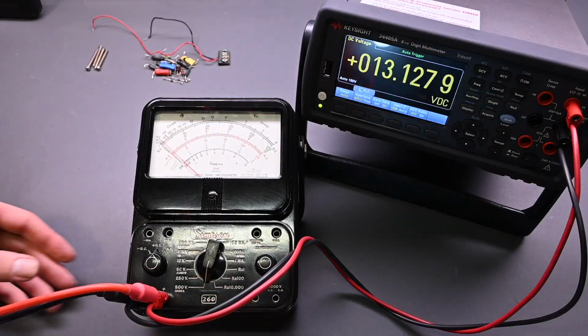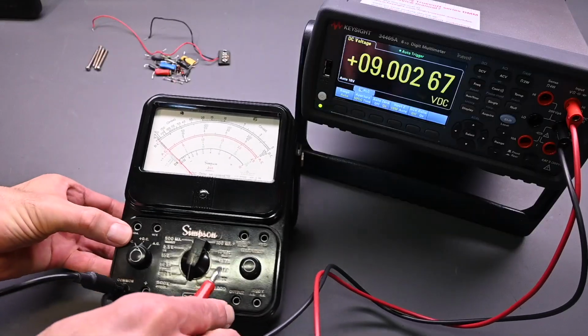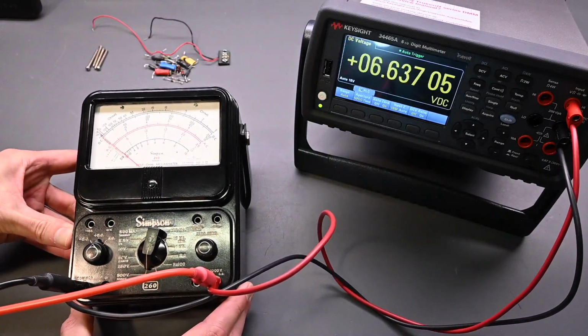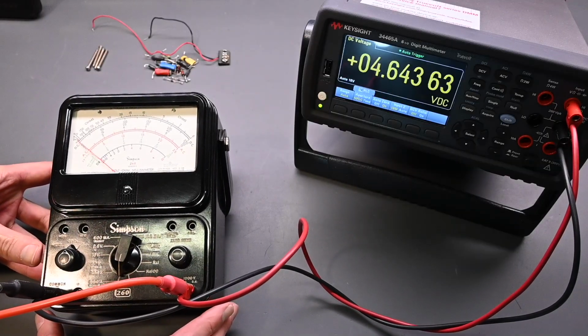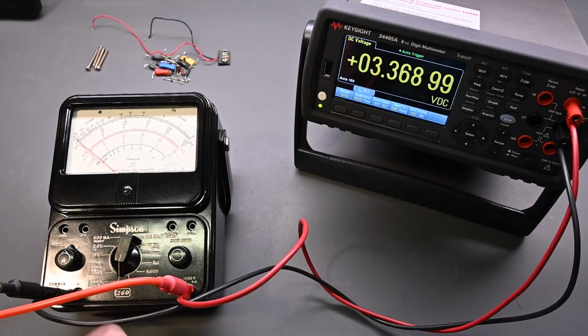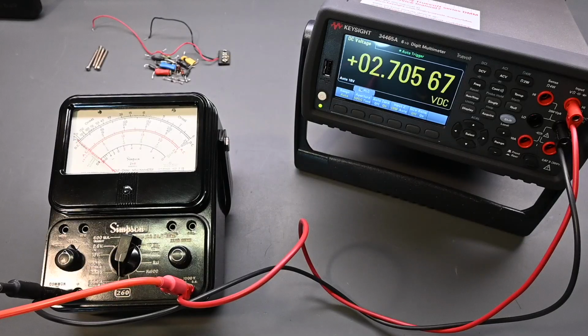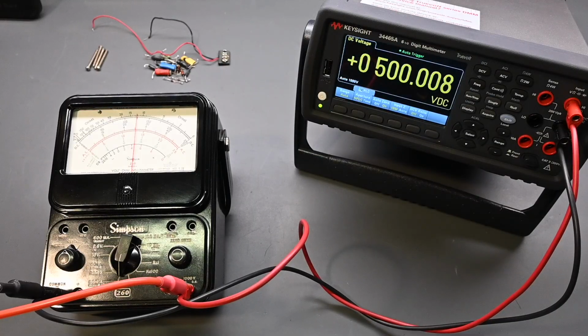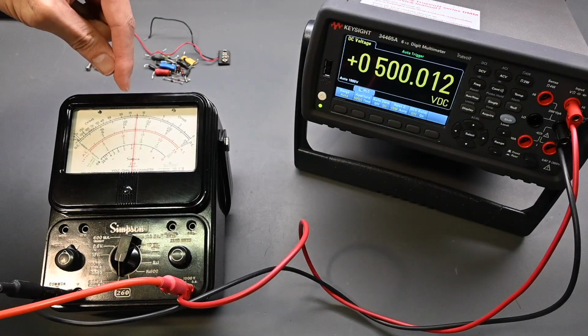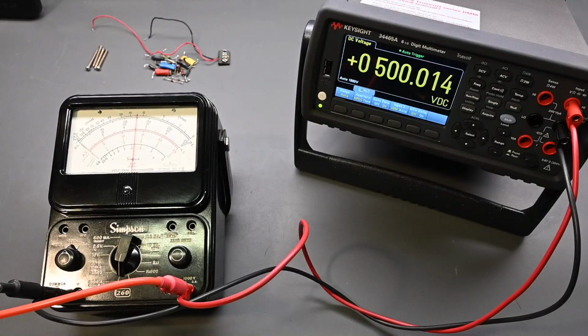All right, so now let's move this over here to the higher voltage position. So this is 1000 volts full scale. My test leads here are not quite long enough. I need to move the meter over just a little bit like so. Okay, so we're on 1000 volts. There we go. So I'll take this up to 500 volts again. Close enough, no problems there. Let's see how this looks. Great. It's right on midpoint, halfway. So the accuracy is spot on. So let's take it all the way up to 1000 volts.